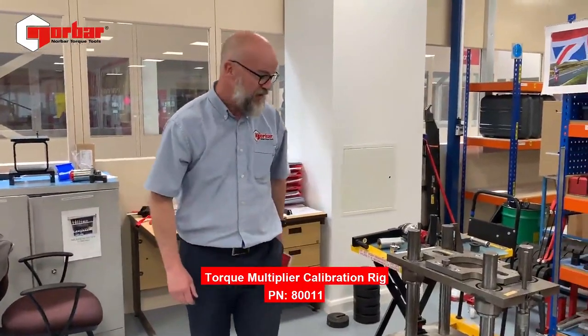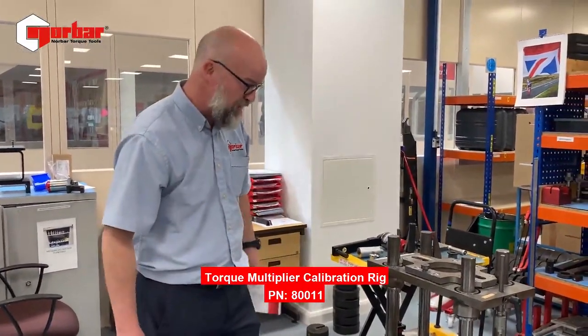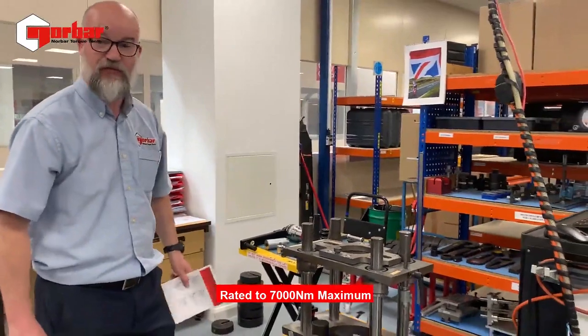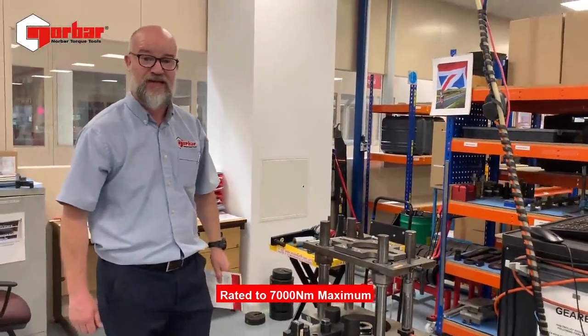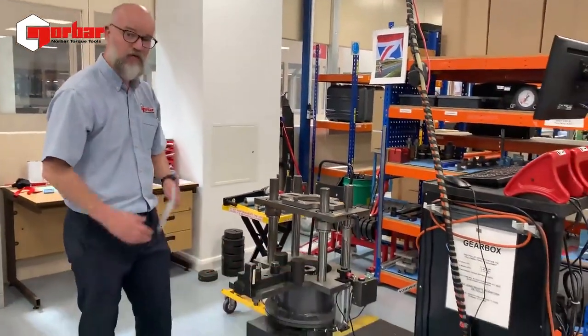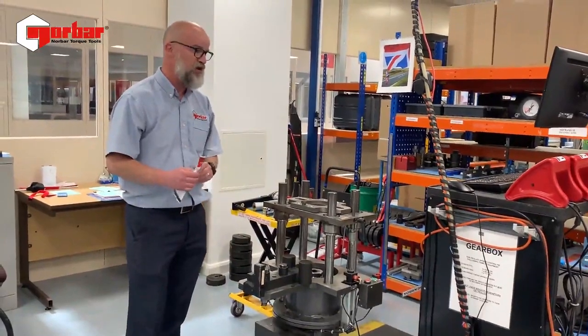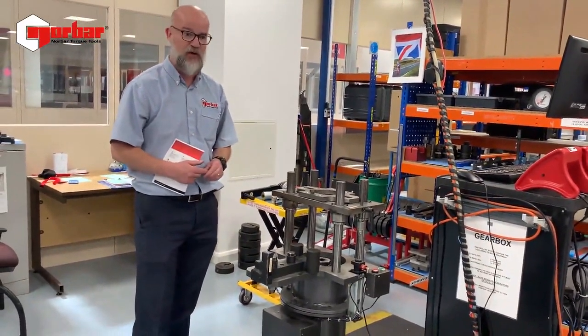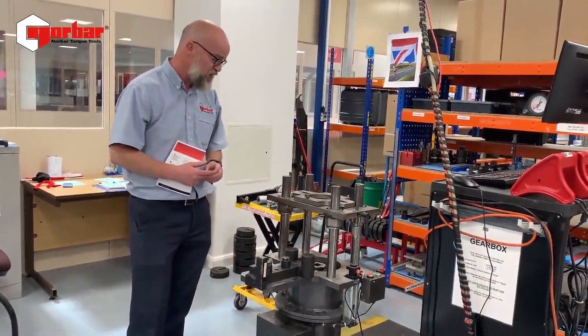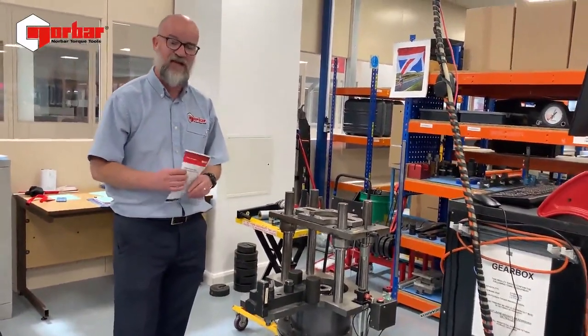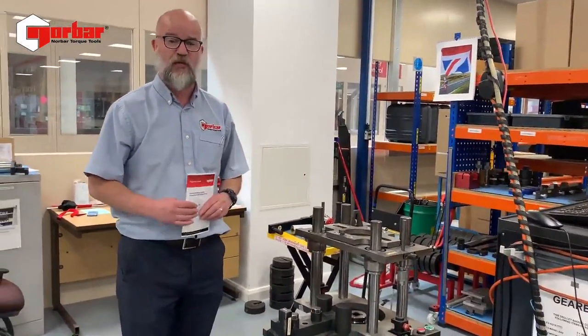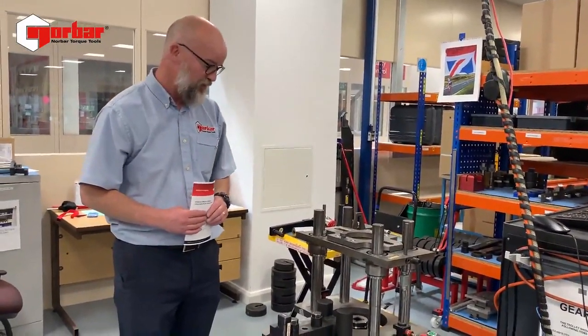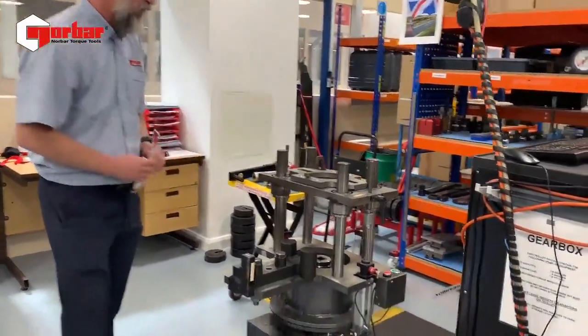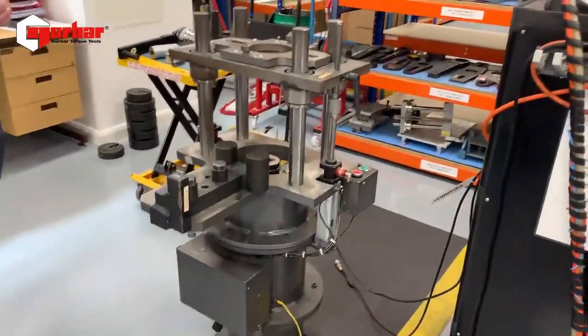Right, we're looking at the 80011 HandTorque multiplier, a device which is rated to 7,000 Newton meters maximum on the output torque. The rig itself is used for the calibration of the ratio of the HandTorque multipliers, and to do that you would need a multitude of transducers and adapters, most of which would have been supplied with the piece of equipment itself.